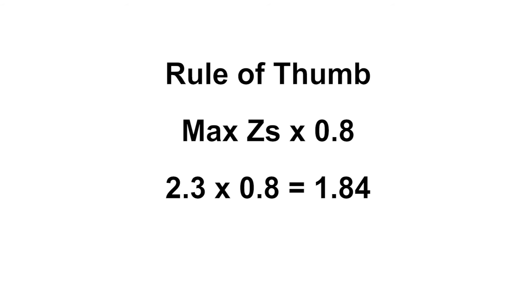For our purposes, if we multiply the maximum value from BS7671, which for a 20 amp type B device is 2.3 ohms, by 0.8, we end up with a value of 1.84. Our measured value must not be greater than that rule of thumb value.